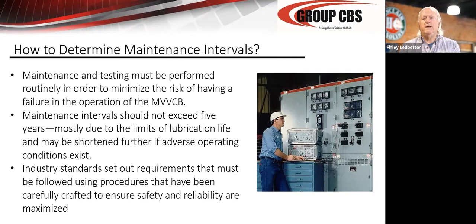But I think that lubricants play the major part of this. 85% of the failures we see are due to lubricant failure. The other 15% are scattered between a bunch of different factors. But if you're using a quality lubricant, you're not letting people combine lubricants, because if you mix lubricants, it's a real problem. You're not using any light spray oils or penetrating greases, and you don't let your maintenance people come in and spray anything in your breaker ever. If you basically take care of it, use the proper grease and lubricants and keep it clean, you should not have any mechanical issues till you get up to the 2,000 or 3,000 operation point in modern vacuum breakers. Like I said earlier, at about 3,000 operations, the world begins to go backwards on you because bearings, pawls, fits, and bushings start to wear. And there has to be some pretty heavy maintenance at about 3,000 operations.